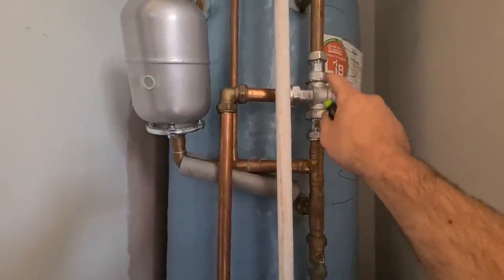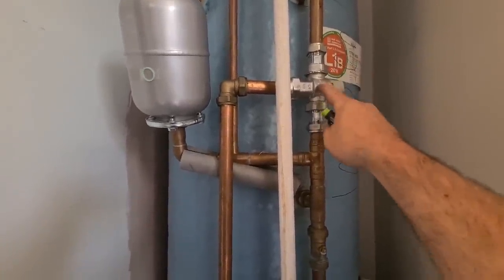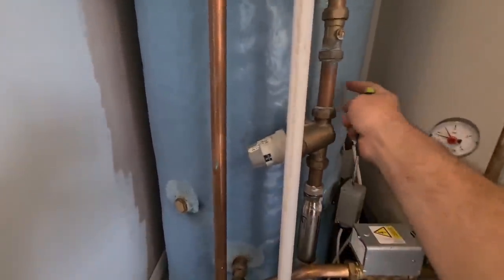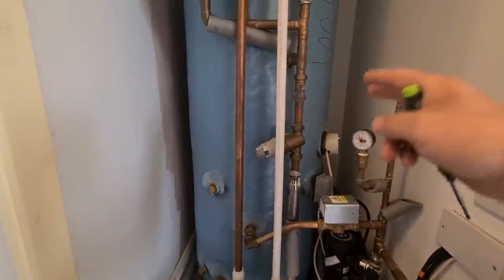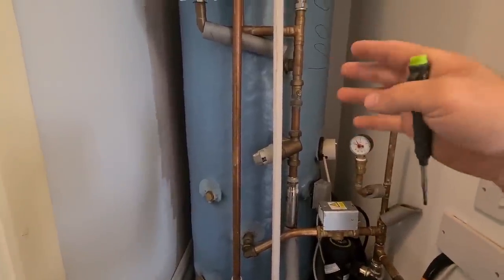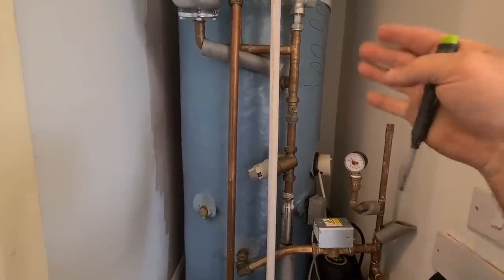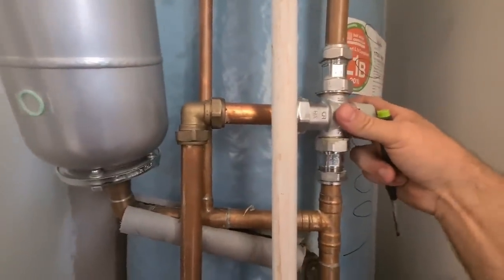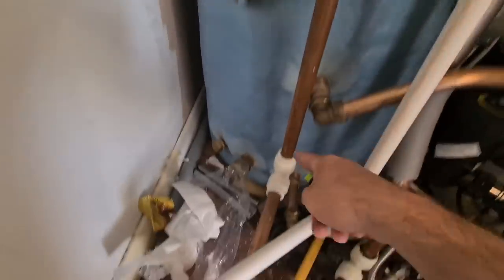Now this is a TMV, a thermostatic mix valve. What it does is blend the hot water, because this cylinder needs to be getting up to 80 degrees, the same temperature as the boiler basically. Running at 60 degrees doesn't work, it needs to be slightly higher, so it works on the limit stat.